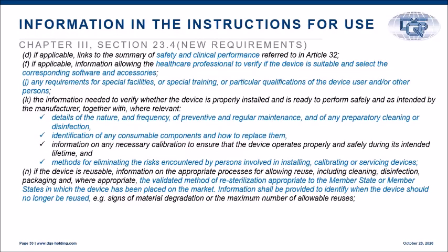So, instructions for use. There are specific new requirements which have come up. I've just touched upon the new requirements in terms of instructions for use. So, safety and clinical performance. You need to give the safety and clinical performance information in the user manual.